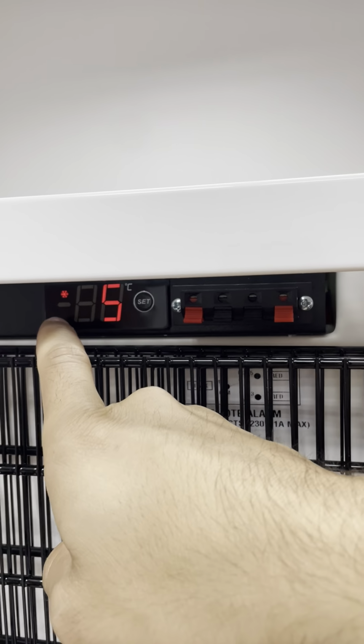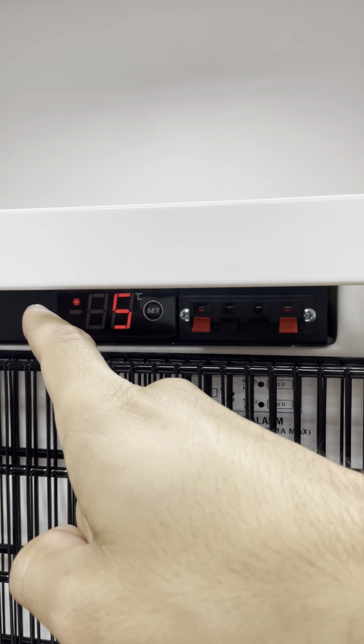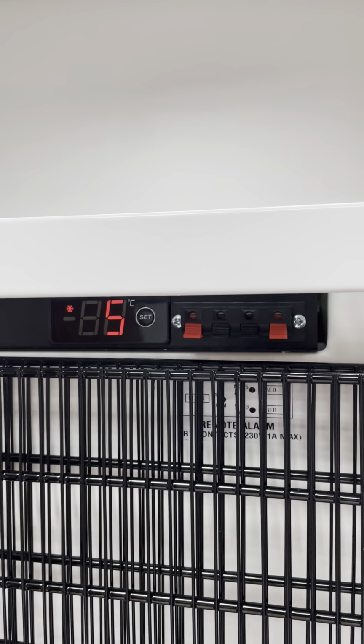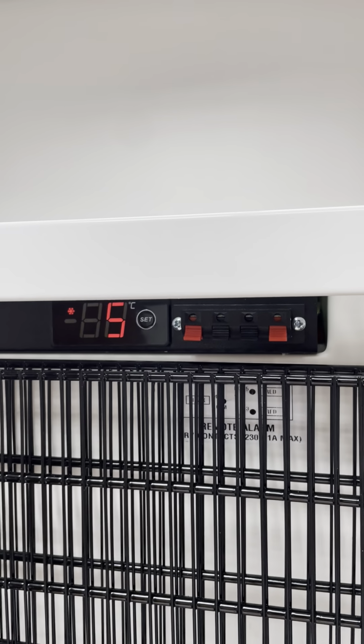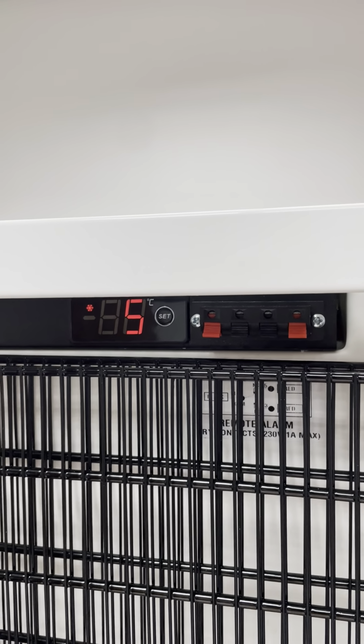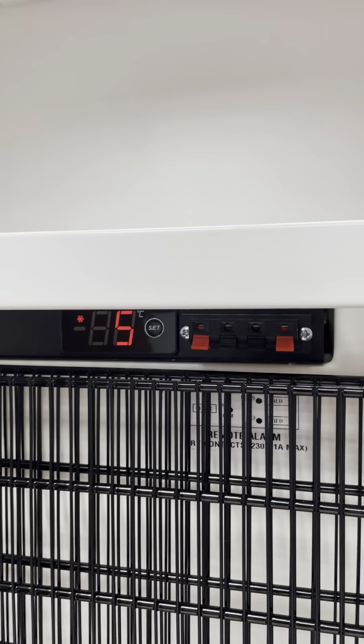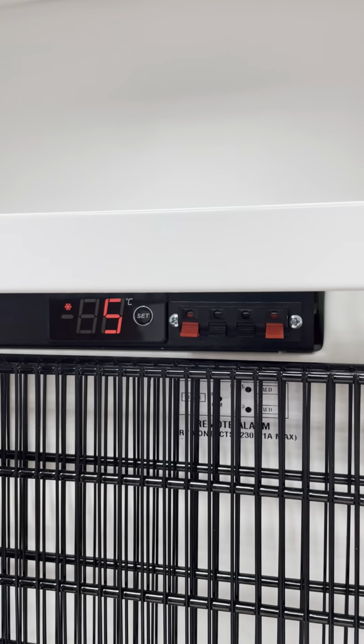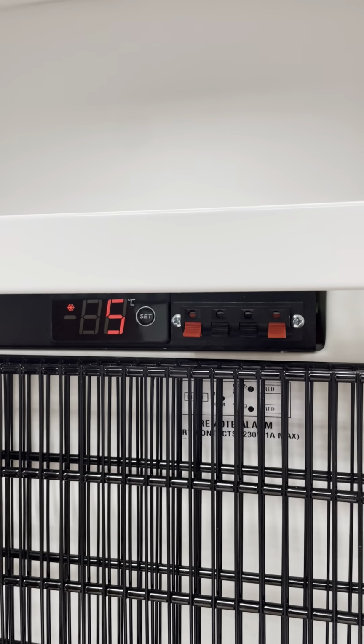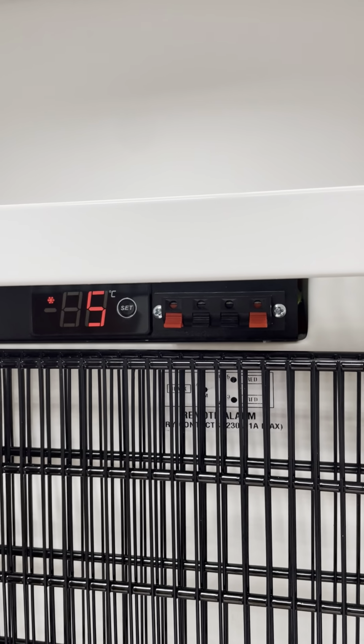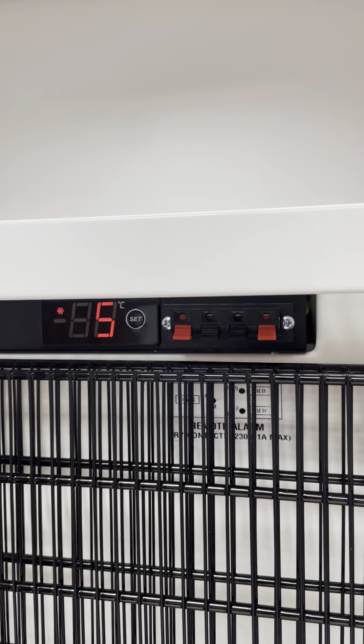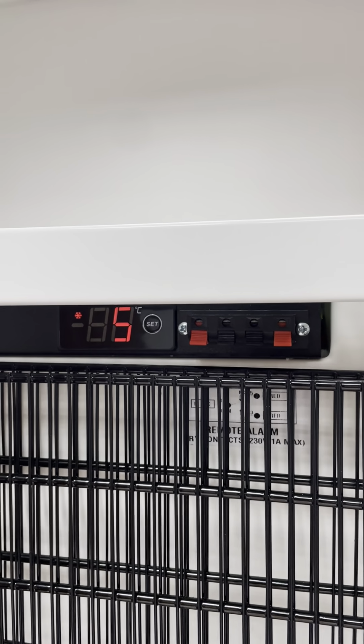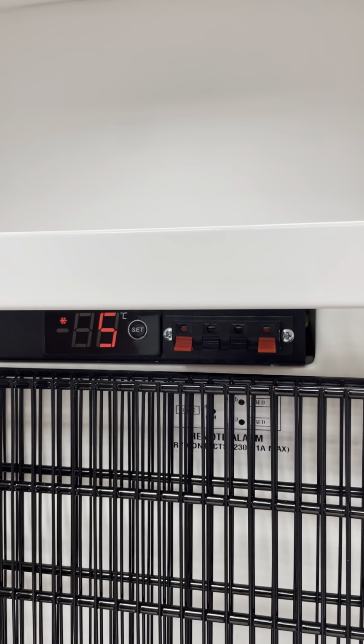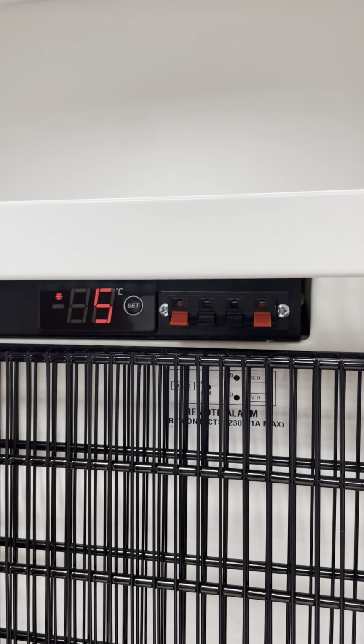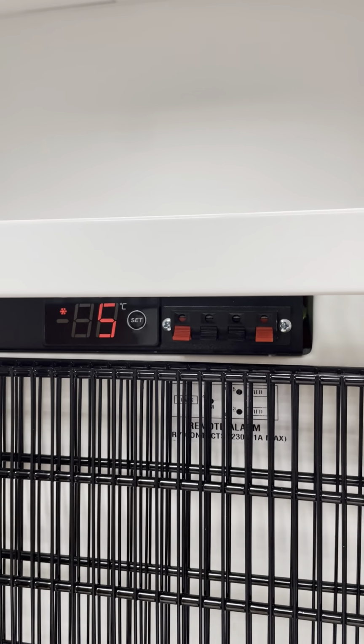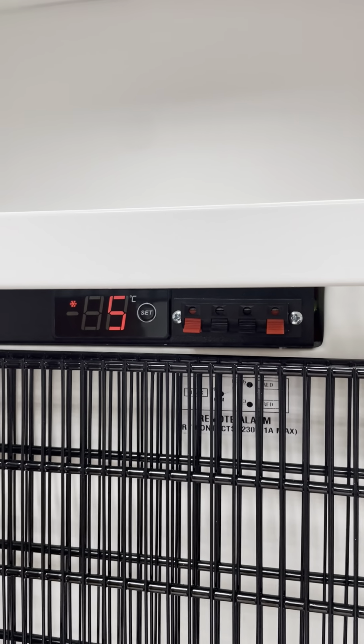And also you have the safety thermostat. This safety thermostat is a digital safety thermostat, and it's very important because this prevents that if anything occurs with the main controller, this will keep the safety of the equipment, meaning if the other one breaks, this will keep the temperatures all the time above 2 degrees. So this not allow the equipment to go below 2 degrees, and this way your medicines will not be damaged by too much cold on the equipment. So this is the safety thermostat that will do this job.